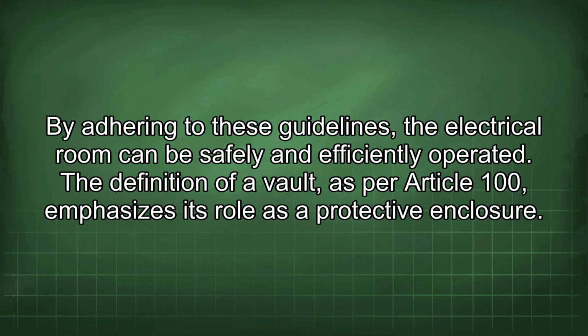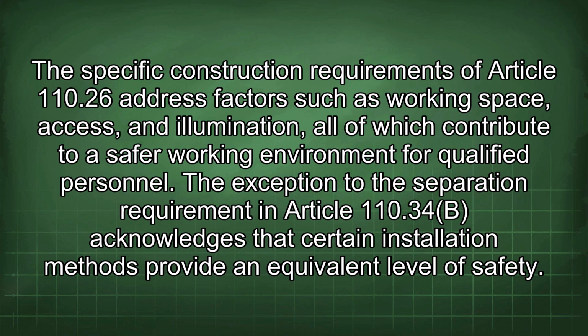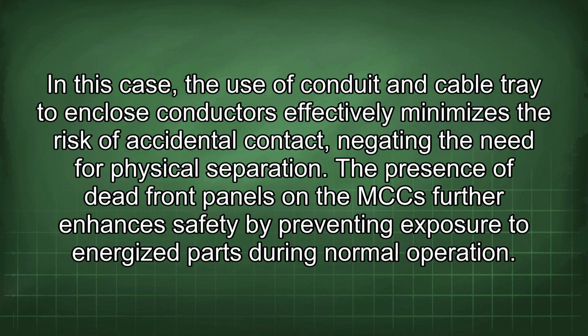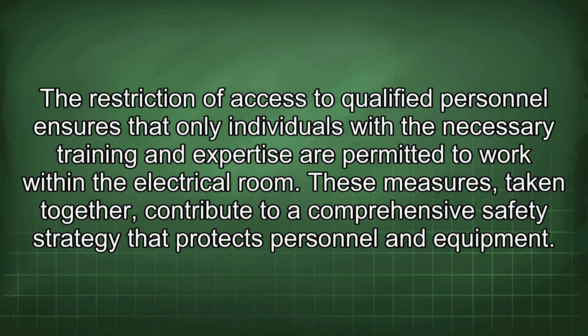The definition of a vault, as per Article 100, emphasizes its role as a protective enclosure. The specific construction requirements of Article 110.26 address factors such as working space, access, and illumination, all of which contribute to a safer working environment for qualified personnel. The exception to the separation requirement in Article 110.34b acknowledges that certain installation methods provide an equivalent level of safety. In this case, the use of conduit and cable tray to enclose conductors effectively minimizes the risk of accidental contact, negating the need for physical separation. The presence of dead front panels on the MCC further enhances safety by preventing exposure to energized parts during normal operation. The restriction of access to qualified personnel ensures that only individuals with the necessary training and expertise are permitted to work within the electrical room. These measures, taken together, contribute to a comprehensive safety strategy that protects personnel and equipment.